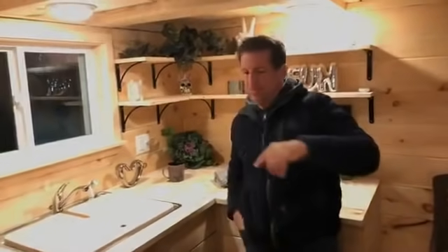One of these right here, just like Sharon was saying, they actually gear down. This is a 9,000 BTU unit. If you factor in the windows, which are insulated, and the spray foam, it's different than insulated fiberglass batts, because that's not going to be as efficient. But when you put the spray foam, the windows, the insulated doors, and the insulated floor, that causes it to work less. Now, it's 9,000 BTUs, but that doesn't mean every time you kick it on it blows 9,000. They actually got a computer in there that gears down. If it doesn't need 9,000, it goes to 6 and 3 and gears back down, so it adjusts to what you have.